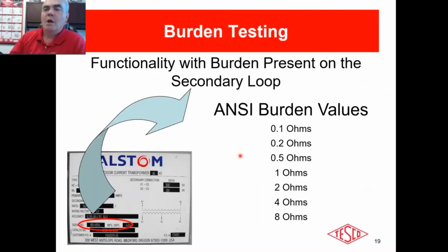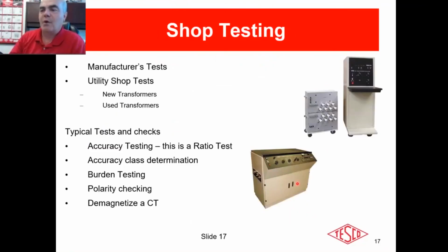All right. These are our ANSI burden values. Okay, 0.1 to 8. There actually are some new ones that have been created in recent years for extended range transformers. We're not going to get into that tremendously here. Not overly important. But there are a series of ANSI burden values. If somebody does an ANSI test, typically you're running through all of those different values. So when you're doing that, like for example in the lab, there is a setting here where you can run through all of those different values.